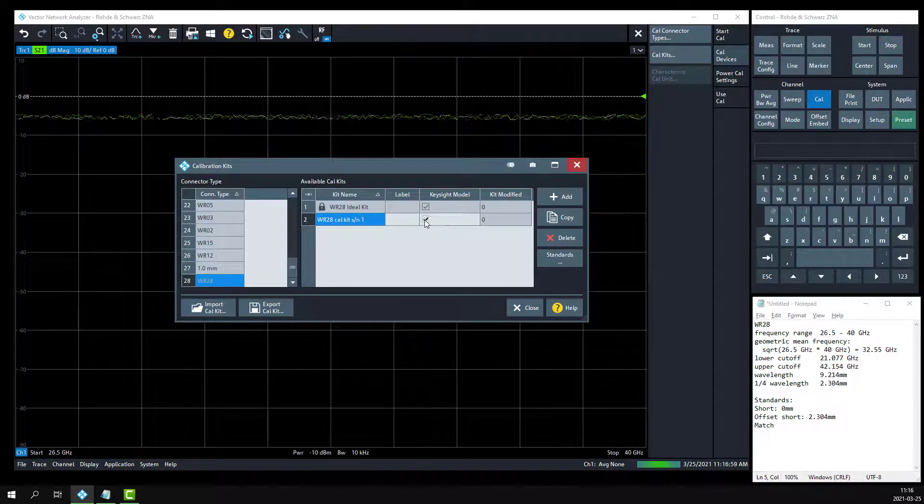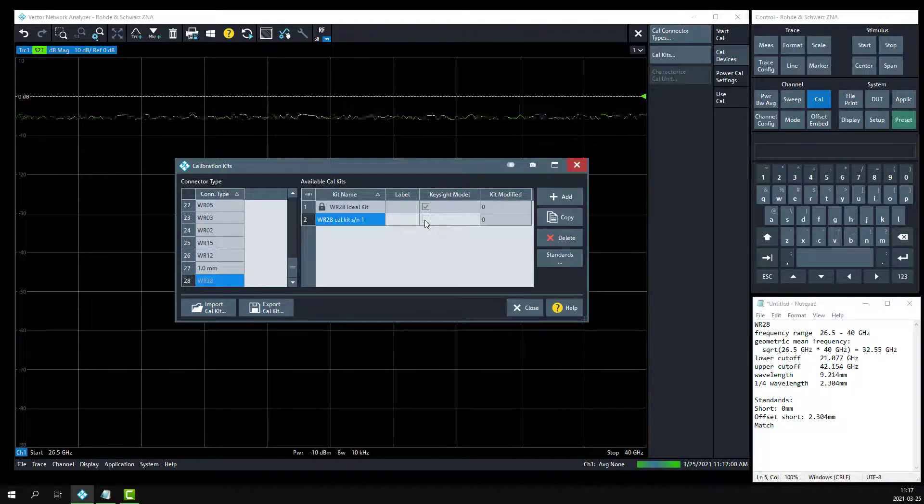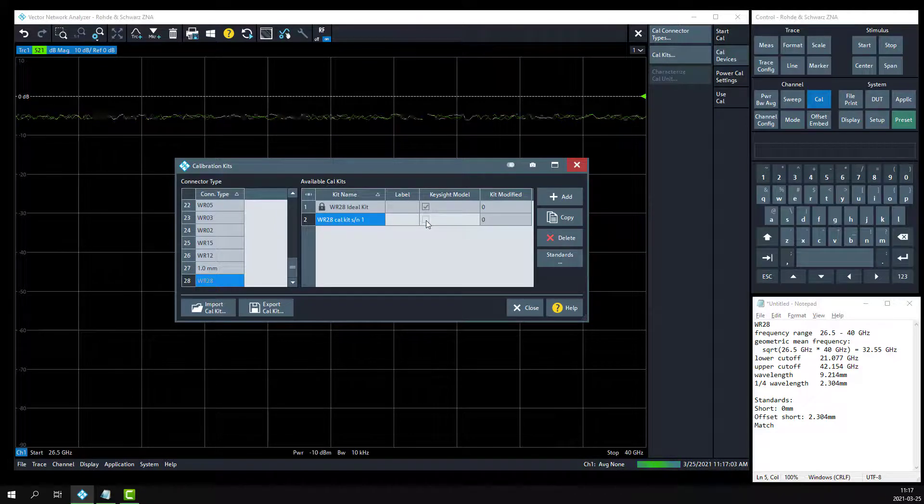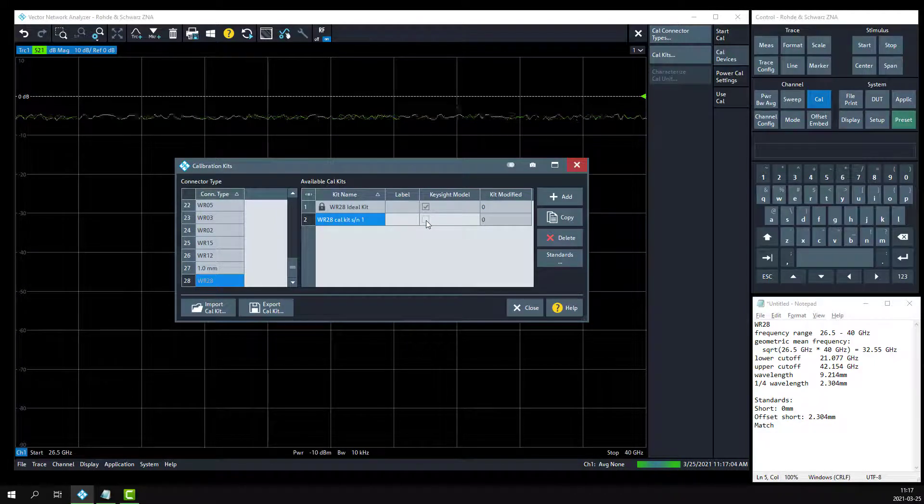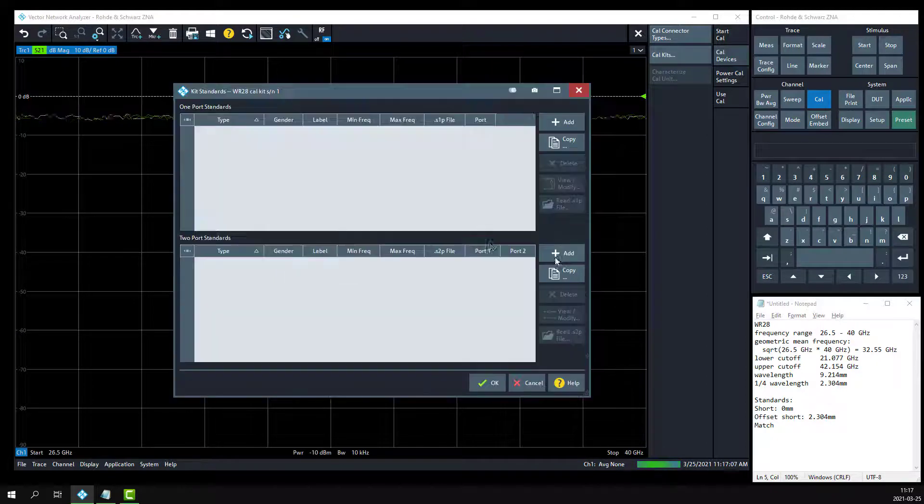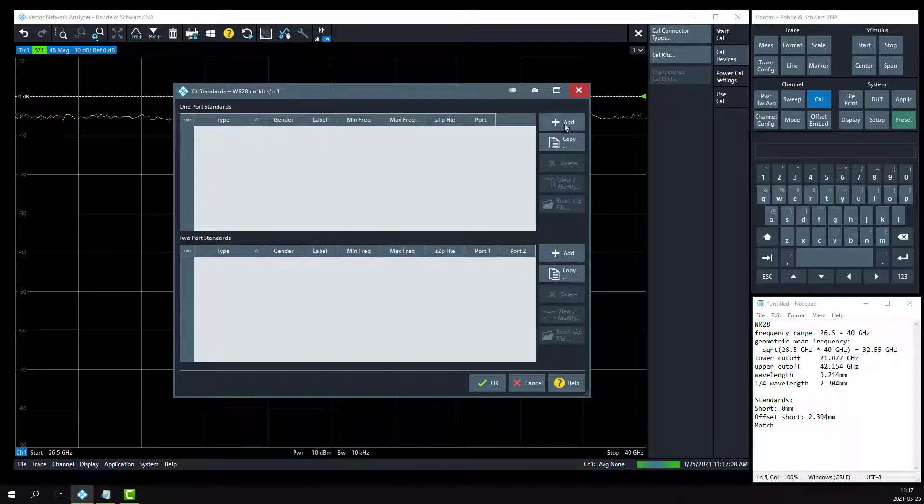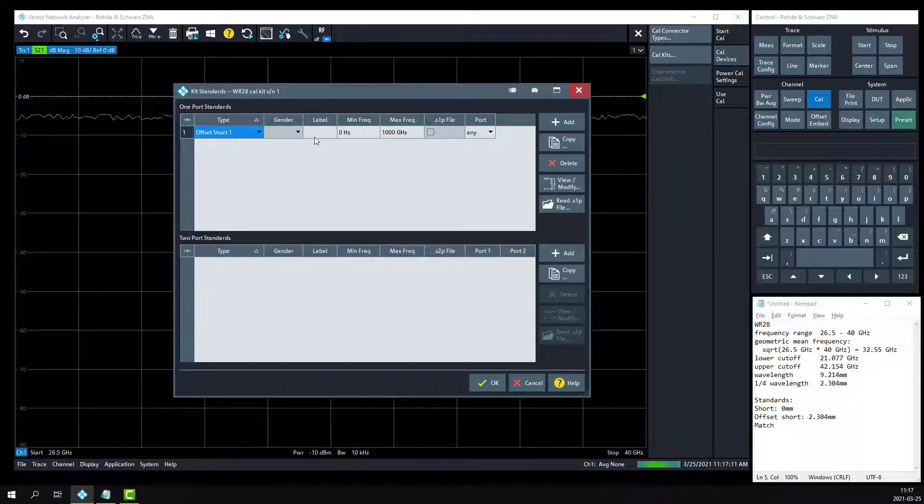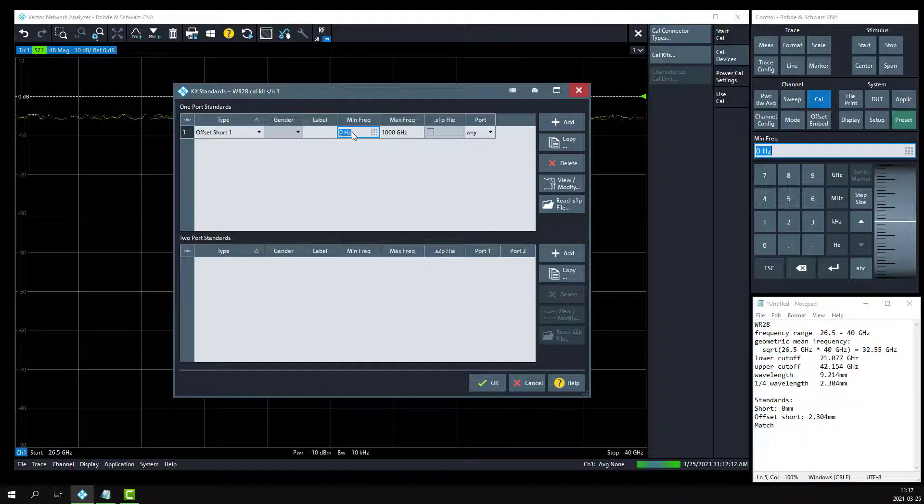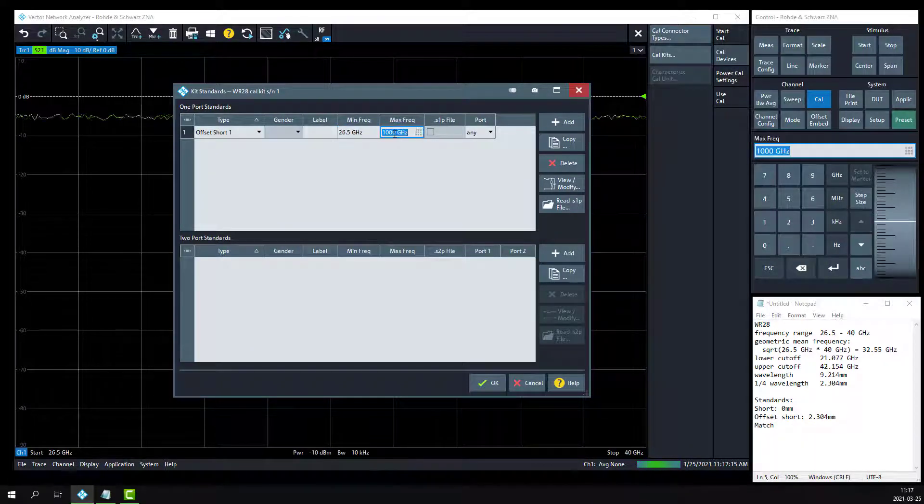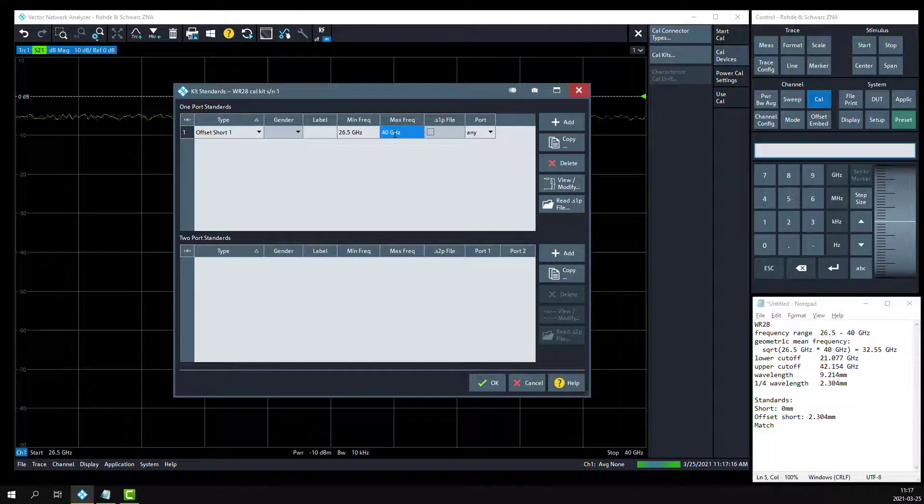We're going to uncheck the Keysight model because we're specifying the offset short as a unit of distance, not as a unit of time. Click on the standards button, and we'll add in that offset short with a minimum frequency of 26.5 gig and a maximum frequency of 40 gig.